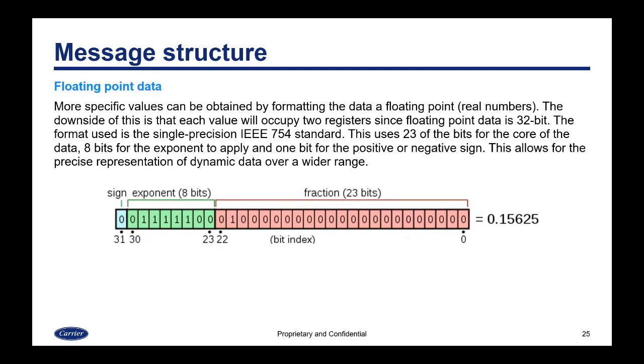More specific values can be obtained by formatting the data as a floating point number, or real number. The downside is that each value will occupy two registers since floating point data is 32-bit. The format used is the single precision IEEE 754 standard. This uses 23 of the bits for the core of the data, 8 bits for the exponent, and 1 bit for the positive or negative sign. This allows for the precise representation of dynamic data over a wider range, and because it uses the IEEE 754 standard, the PLC will have an accompanying data format.